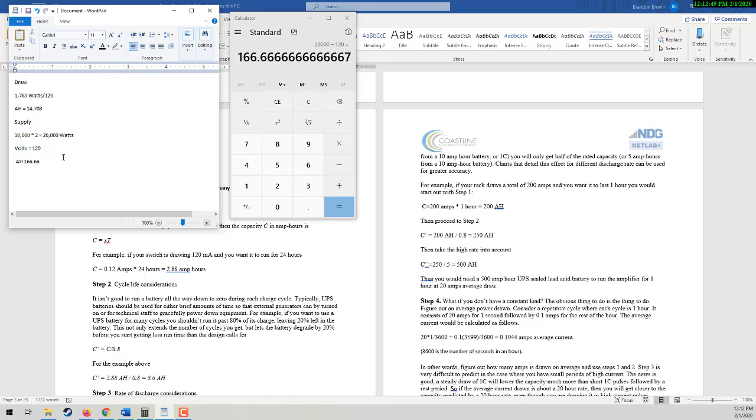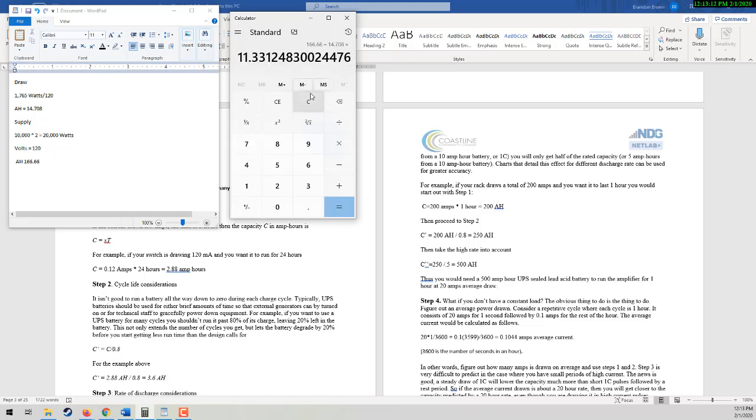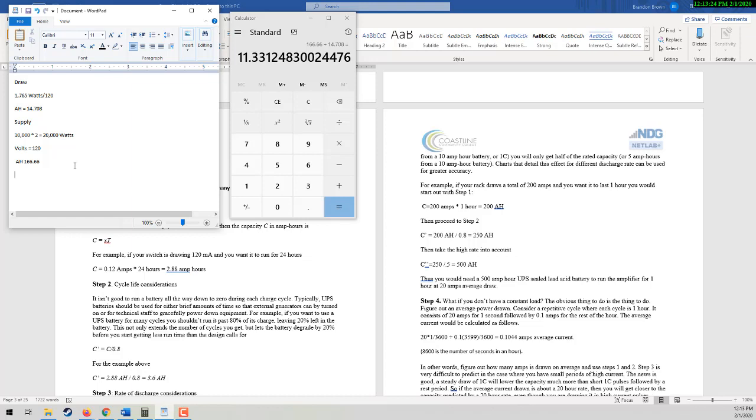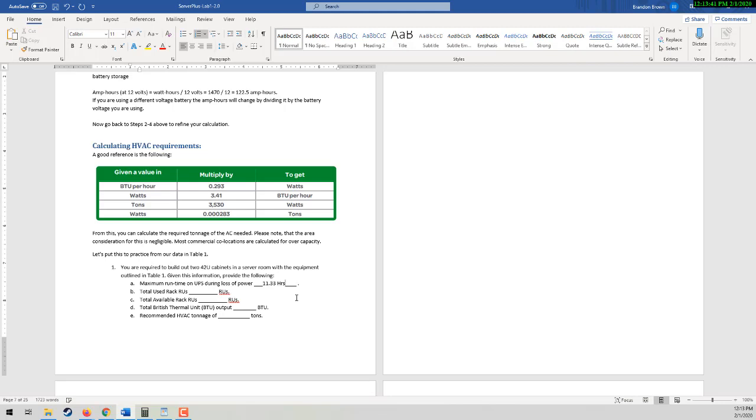So we now have our supply and we now have our draw. They're in amp hours. So if we then just simply do the calculation of draw into supply, that gives us 11 hours. So our 11.33 gives us the run time of our UPS during the power outage. Now the rest of these are pretty straightforward.